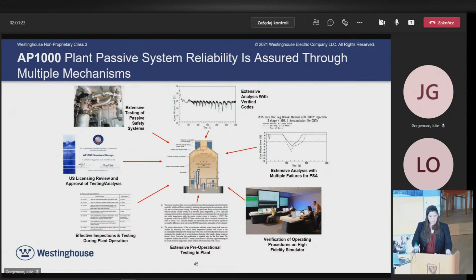You can measure how much heat is being transferred to a tank inside containment, for example, or what the flow rate is in natural circulation for some of those loops. All this is measurable. So during the startup program, the initial final verification before starting up the reactor, we can verify the performance of those systems, and continue doing so through the periodic testing program at the plant.